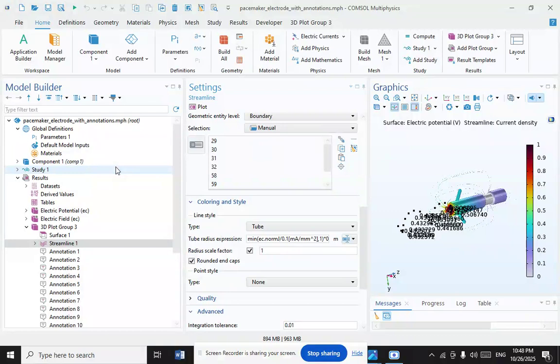An important aspect of pacemaker function is sensing the intrinsic heart activity. This is called sensing. Larger sense voltages are desired, and it's expected that the ventricle produces a larger voltage than the atria. The minimum voltage to sense an event is called the sensitivity. The higher the sensitivity value, the less that is sensed, and vice versa. Too low a sensitivity value can cause troubles with sensing P waves, T waves, and noise. Sensing these things is called oversensing. A sensitivity value too high may result in missed sensing of P waves in the atria and QRS in the ventricles and is called undersensing.